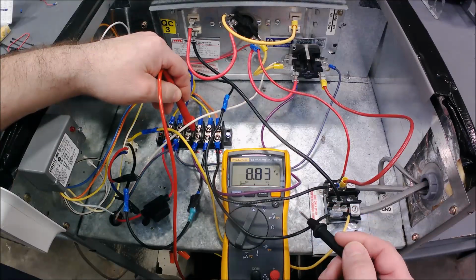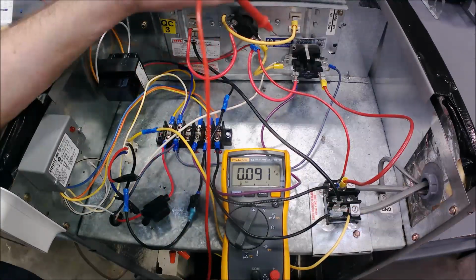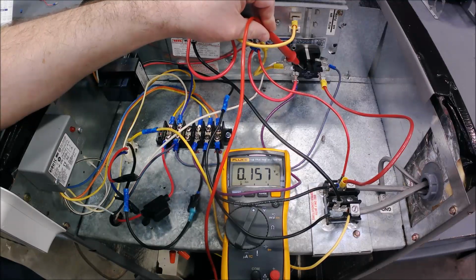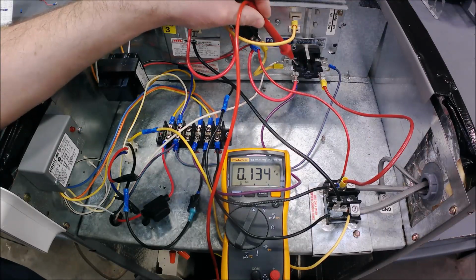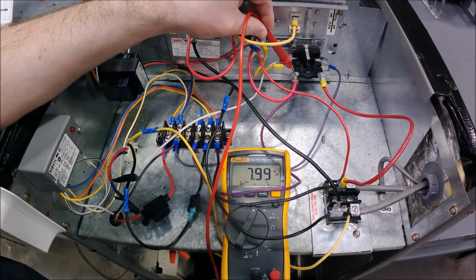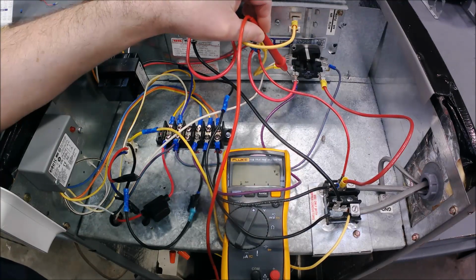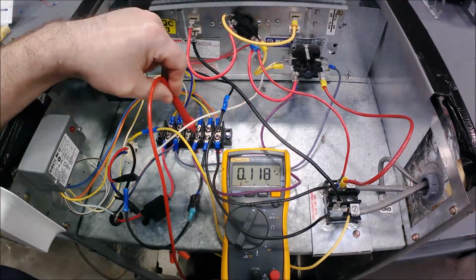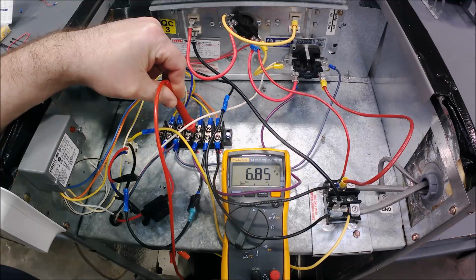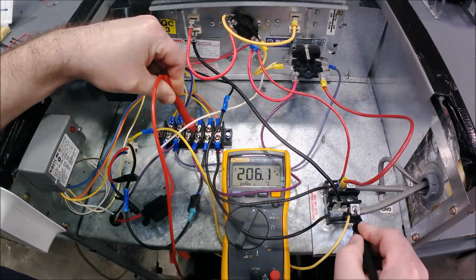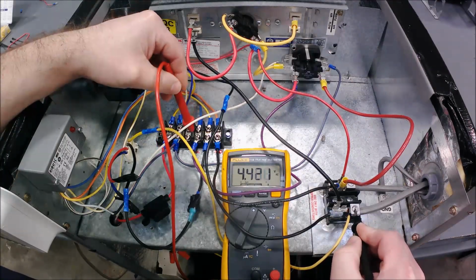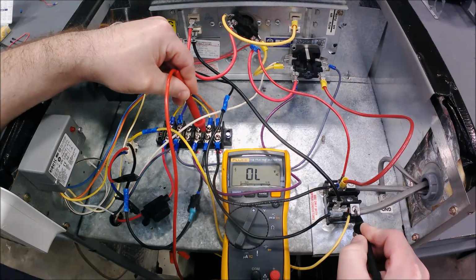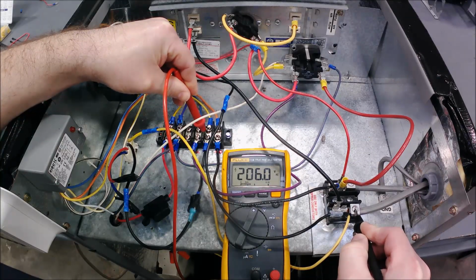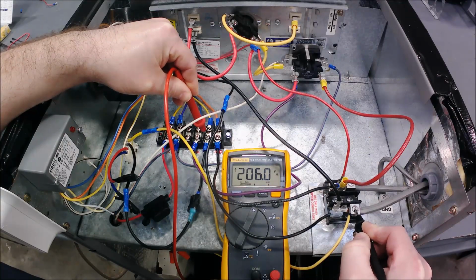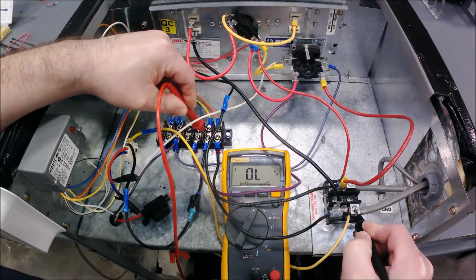The purple has L1 because my heat relay is sending power across the sequencer switch, and when this heater starts, power here on this red wire also sends power down that purple one. So it's also an active L1, you could say. And then my common, being the way out of this rib relay, is my high voltage coming out. So my fan is on, and I've got power on that common too.